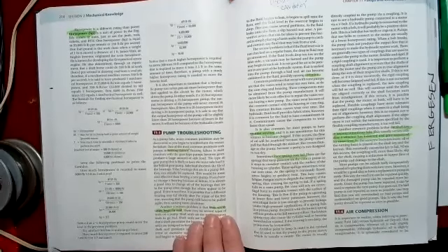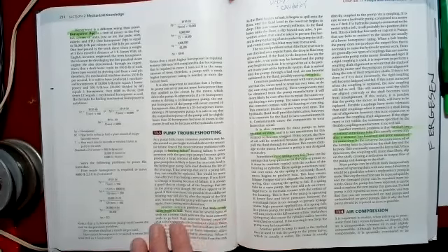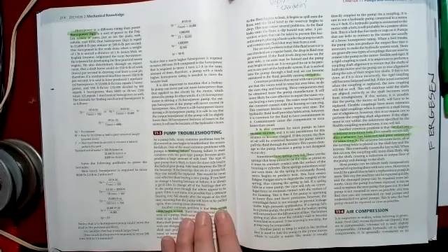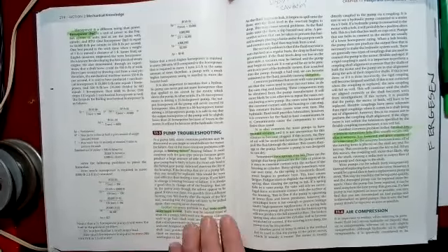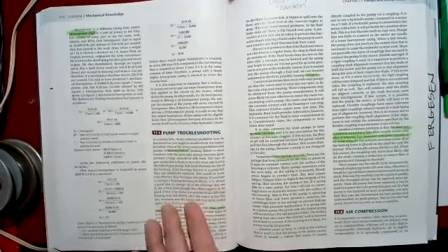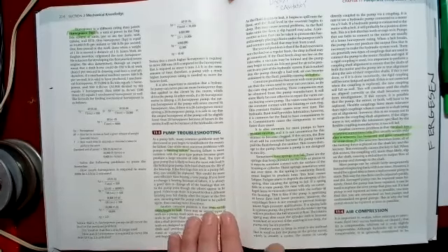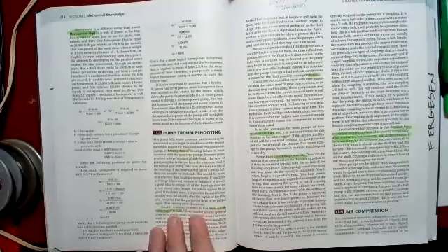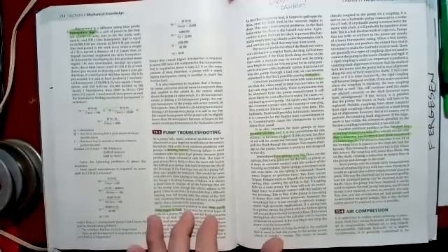The most common reason for pump failure, in my experience, is seals, especially for the piston pumps. Those little valves seat against little seals, and those seals tend to fail over time. The seals will fail faster if you've got more grit or gunk going into that pump, causing problems with the seal of that particular valve or on the outside edge of the pump. So the more dirt you run through a pump, the faster it will fail.